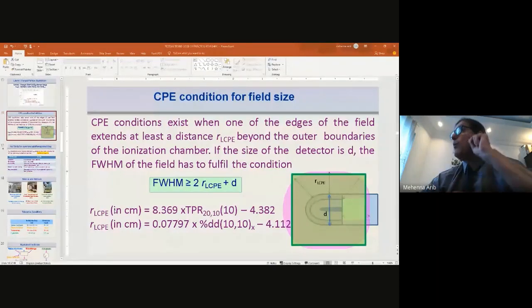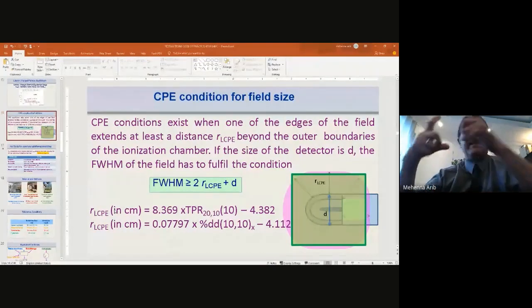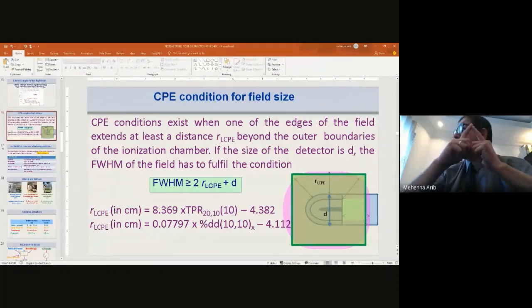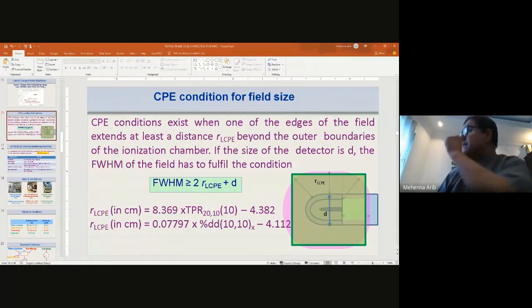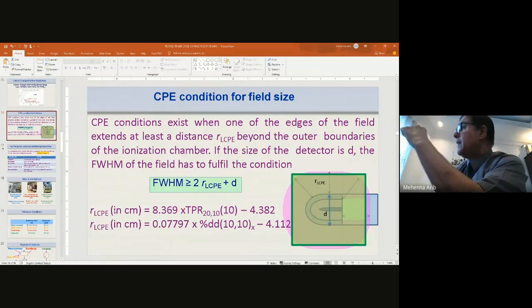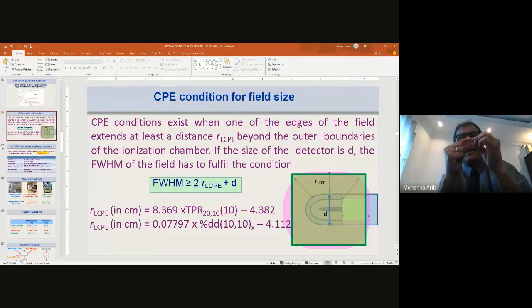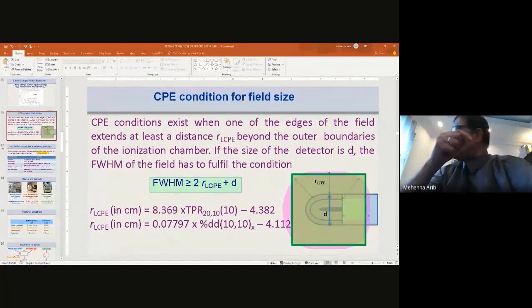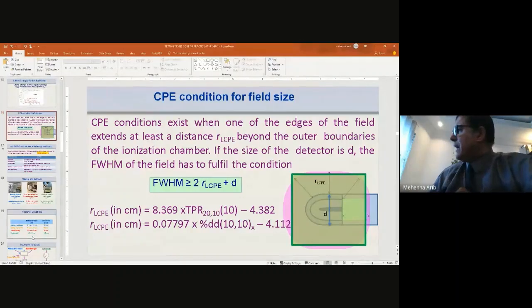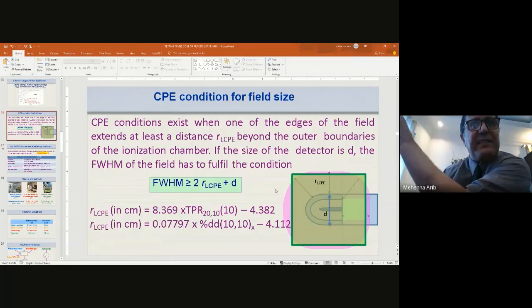This will be more than 2 times. I mean, the field size that you are using should be at least 2 times the lateral equilibrium plus D. What is D? D is the external diameter of the chamber. Be careful. Some chambers have a diameter bigger than the length, so you have to use the bigger dimension. For example, if you have a radius of 5 millimeters but the length is 7 millimeters, the D will be the length. Okay. Yes.